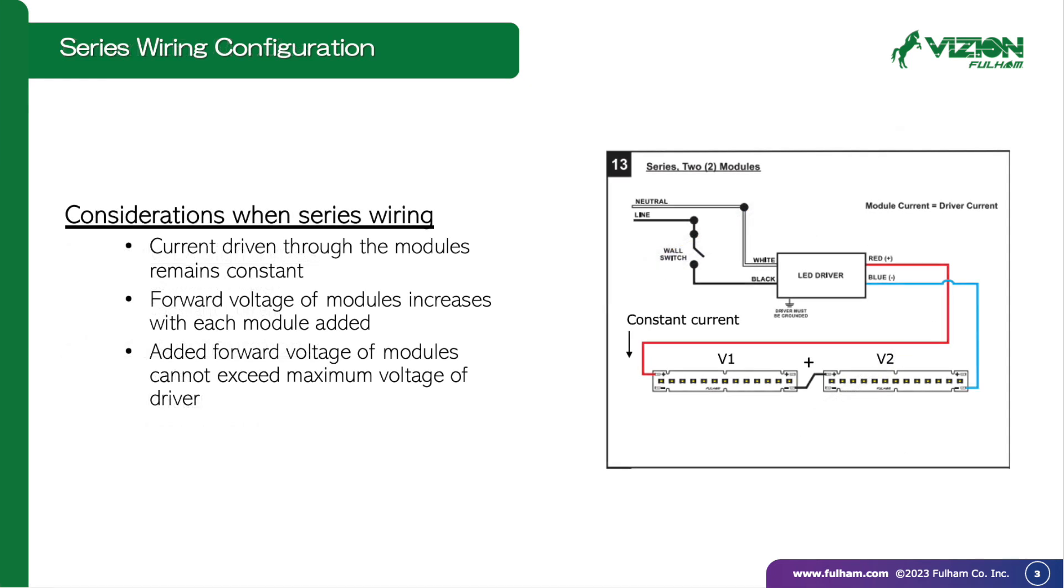In series wiring configuration, the current of the modules will remain constant, while the forward operating voltage of the LEDs will increase with each module added. Because of this added voltage, one must ensure that the total forward voltage of the module does not exceed the voltage of the driver.